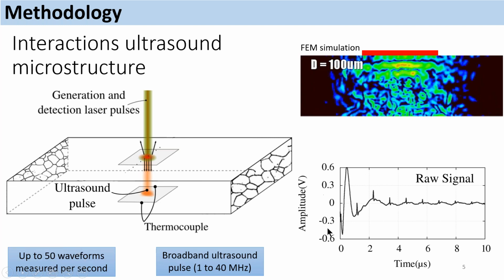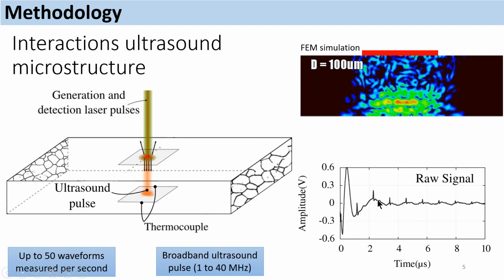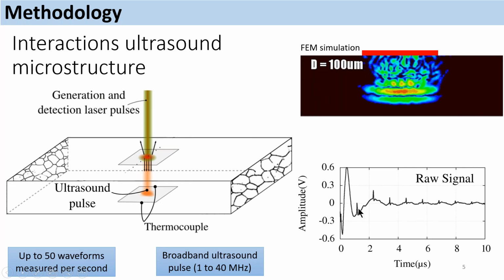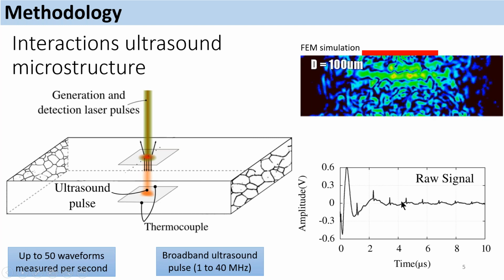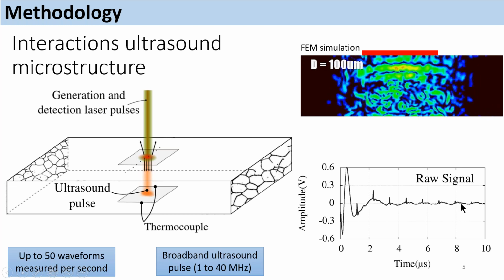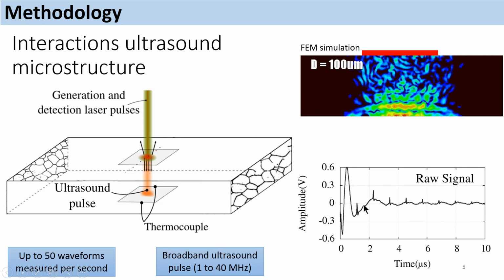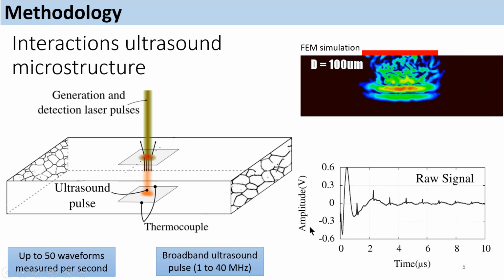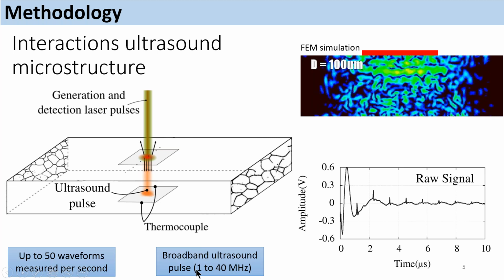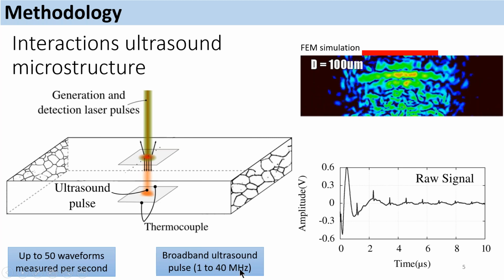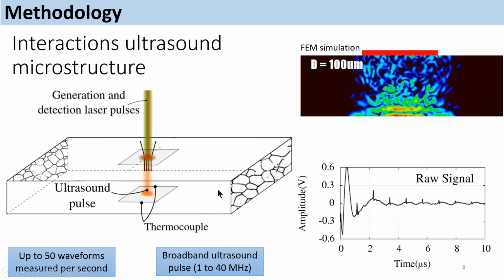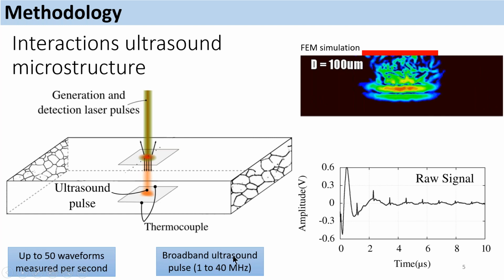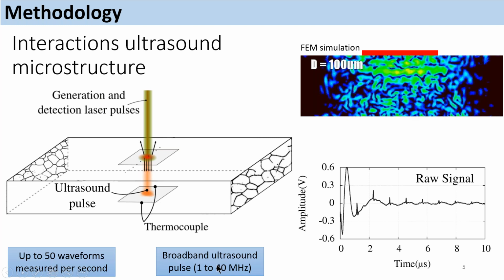So those waveforms can be visualized here, and those peaks that you see on the waveform correspond to the moment in which the pulse comes back at the generation surface. So you can see that we can measure many times the pulse coming back at the generation surface. Another important feature of this sensor is that it generates an ultrasound pulse which contains a broad range of frequencies. Typically, we can access frequencies ranging from 1 to about 40 megahertz. Of course, as we will see, depending on the microstructure properties, those high frequencies tend to be attenuated quite a lot. So the effective bandwidth that we can use can tend to be a little smaller.